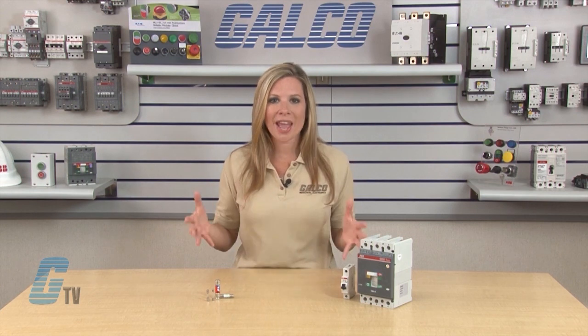Thermal circuit breakers, often found in residential, use a bimetallic strip that expands when heat is applied. Once enough heat has been generated due to an overload, the unit will trip. Residential and industrial markets may also use thermal magnetic circuit breakers, which is a combination of the two.